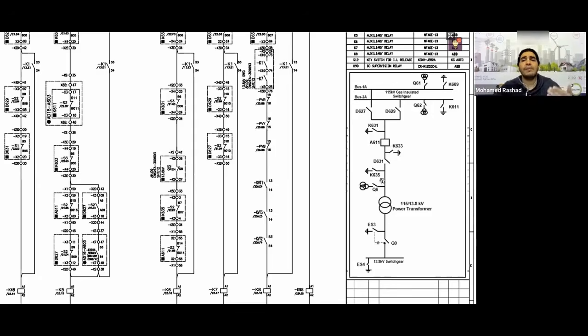So I was doing interlocking between the two stations to check the grounding of the remote station, and take the output contact from the protection relay and put it in the interlocking circuit. But this is a bit excessive. If the operator can see the stations together and can check something like this, then it's fine. And there's another way they do it, which is coordination between the two stations. But I'm telling you, if you want to do it, it's not a problem. If you're just checking the grounds, just 1, 2, 3 are open and the breaker is open, just check that the grounds below are open.